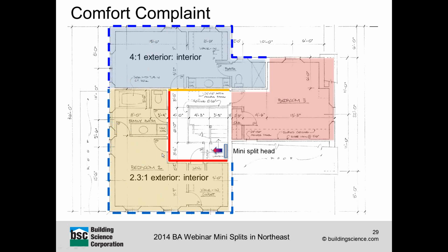If we want to do this type of analysis in more detail, Rob Aldrich from Steven Winter did a very nice job making a spreadsheet of what are the relative heat losses, and you can calculate do what-if scenarios of what the temperature will be in the room with these various surface areas and U values. You add a transfer fan, how does the temperature change? You open the door, how does the temperature change? It's a quite elegant tool.